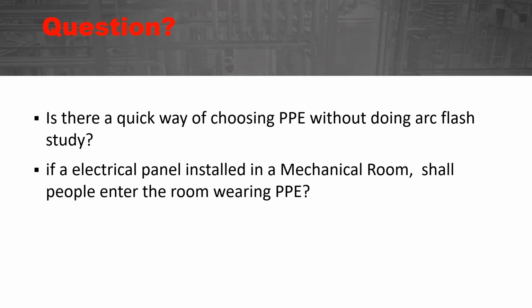To answer the second question, if an electrical panel is installed in a mechanical room, do people entering the room need to wear PPE? Well, that depends on a number of things. Is the door of the electrical panel closed and is it operating normally, with no impending failure? Is the panel across the room from the person, outside, say, the restricted approach boundary and the arc flash boundary? Or are they inside? So the answer is, it depends on what you're doing. If the panel's door is closed and it's operating normally, with no signs of impending failure, then no. But if there's potential for impending failure, then probably. And if the door is open and you're walking right in, violating the restricted approach boundary, even the arc flash boundary, then the answer would be yes. So that depends on your particular situation.